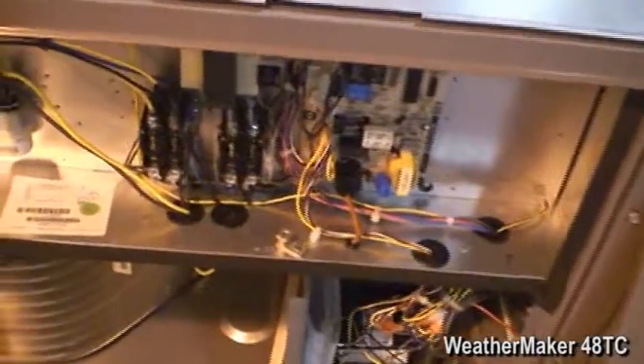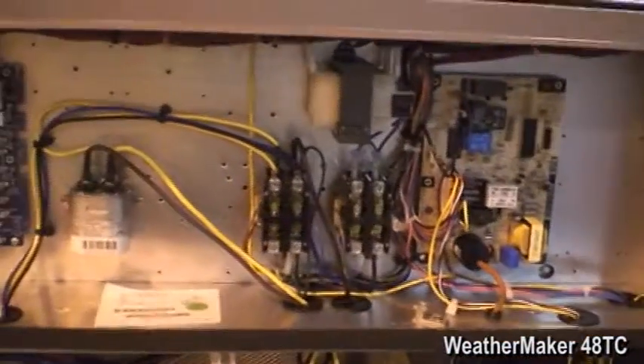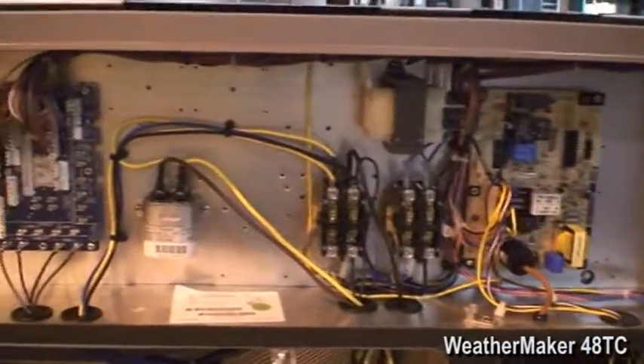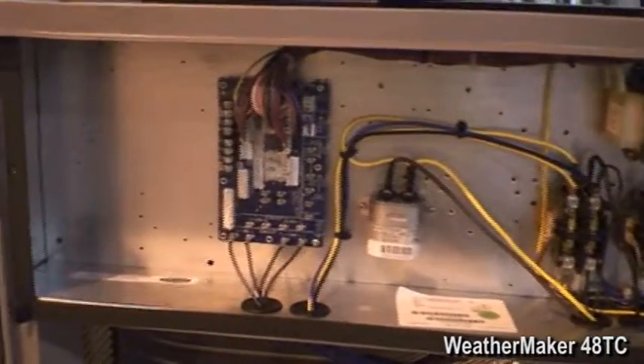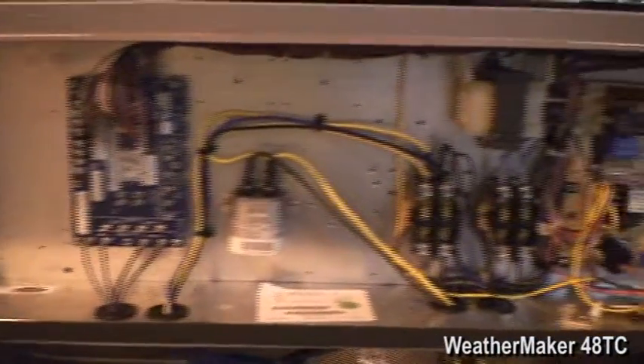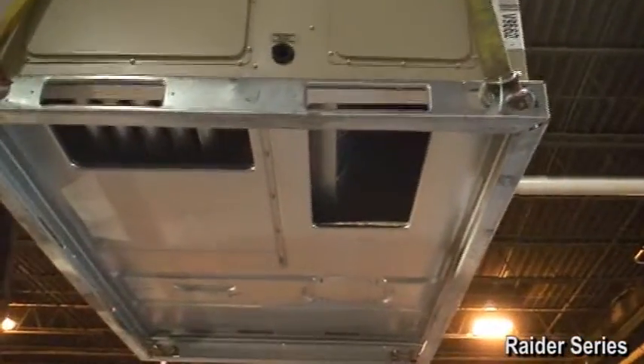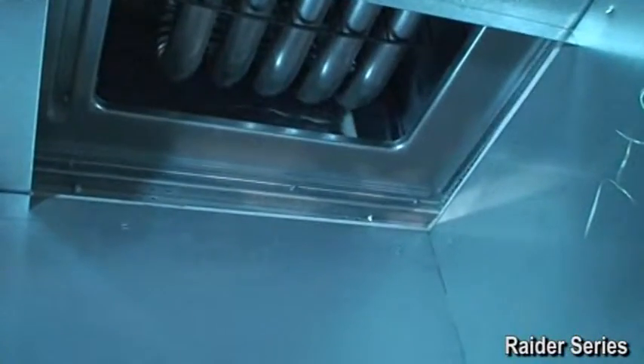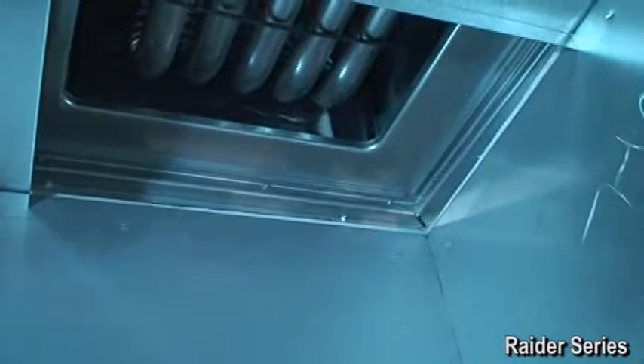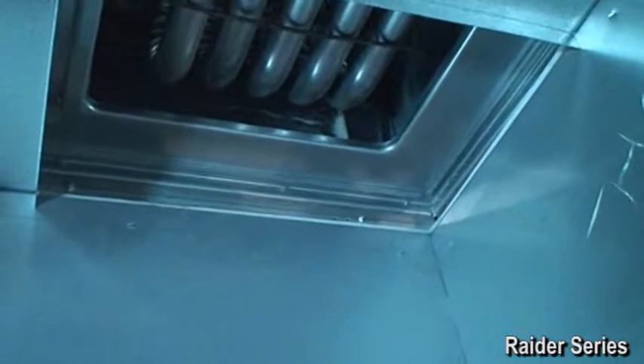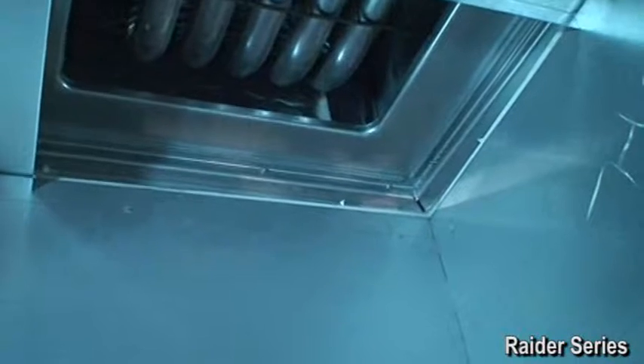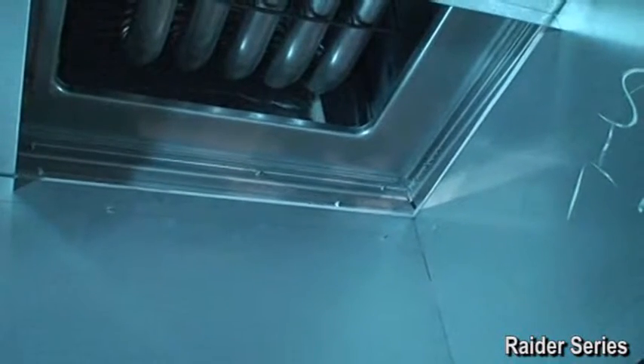All of this leaves you with a well-organized, safe, ease of installation control box that is designed to keep the harsh outdoor elements out that can cause contactor pitting and premature component failure. The last thing the review team looked at on the competitive Raider unit was how the unit fits on an existing or original Carrier roof curb as claims were made. We used a safety stand with an actual mounted curb to see the actual fit up.